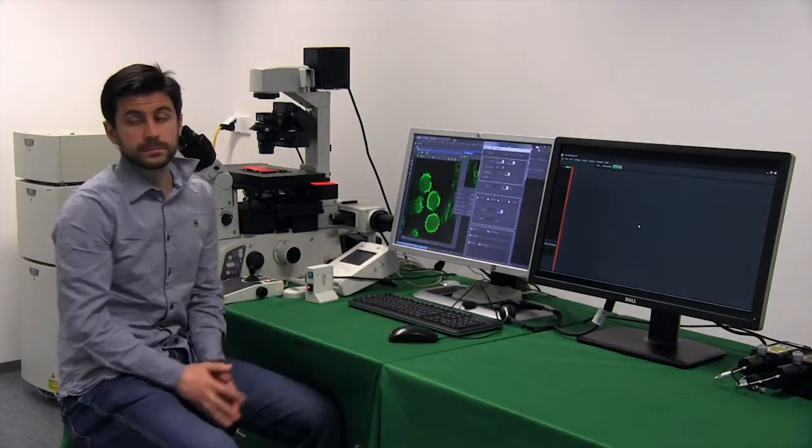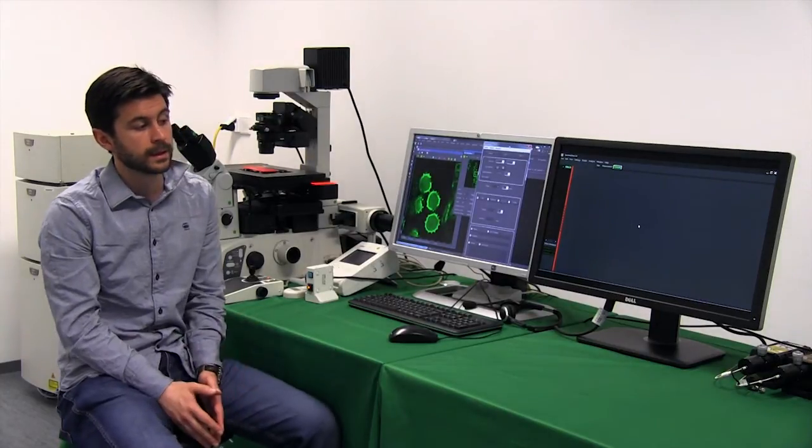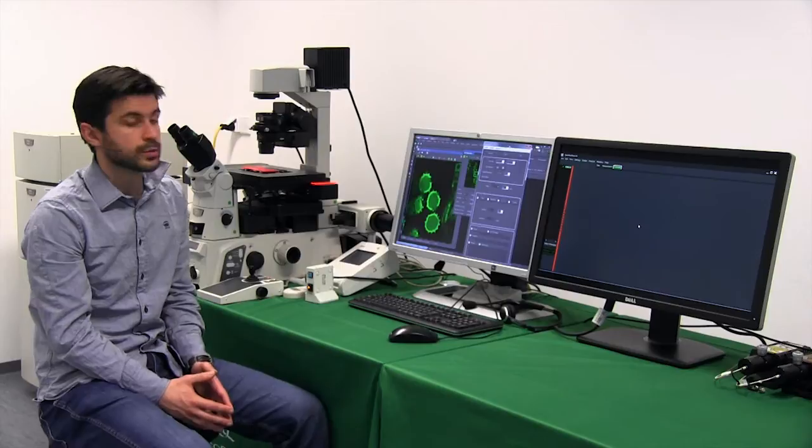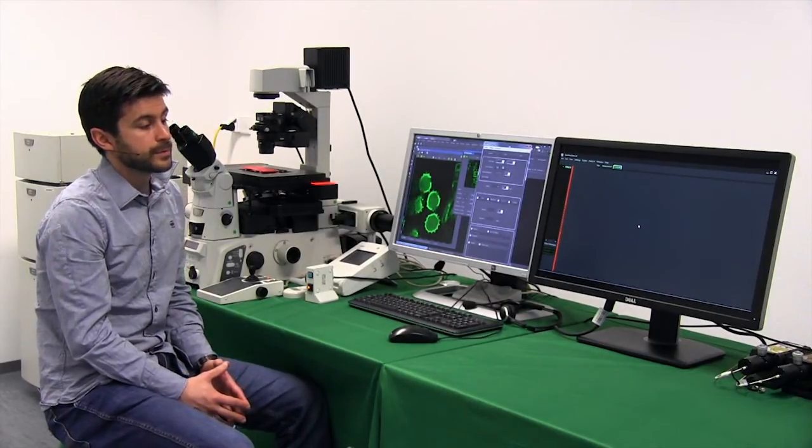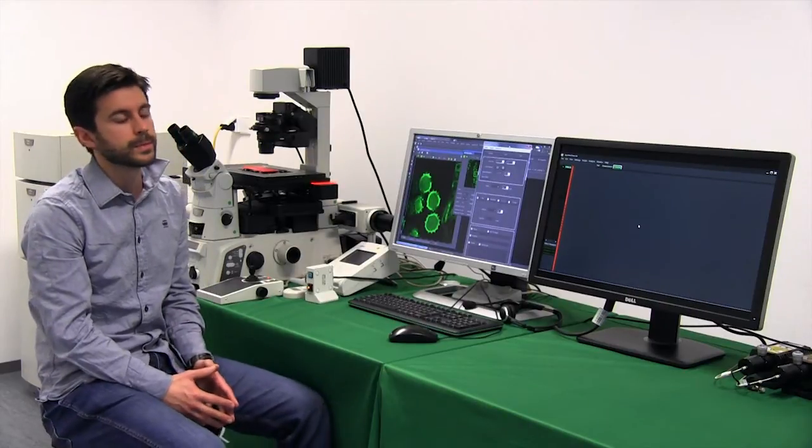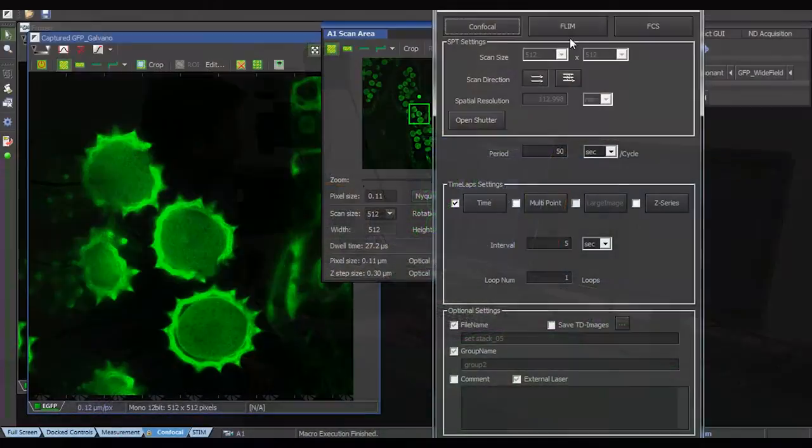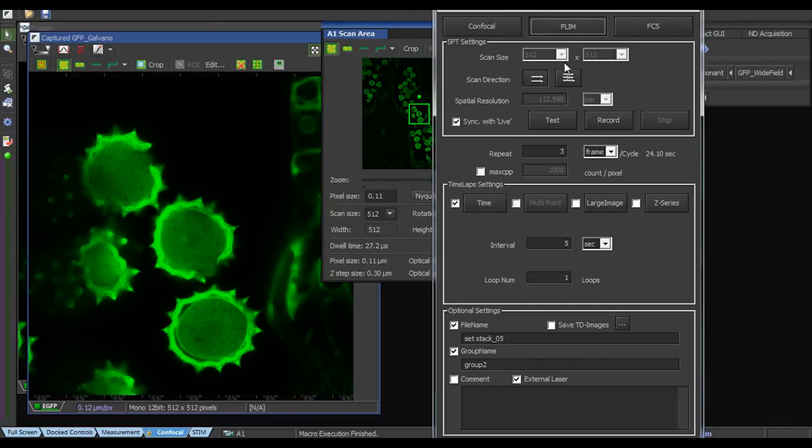In FLIM measurements there are two things we have to control. Most importantly the first one is the repetition rate of the laser we want to pulse with. We have to pick a repetition rate which is low enough to allow the whole population to decay. And the second one is to control the count rate. Due to the dead time of the electronics we have to keep the count rate to 5-10% of the excitation rate depending on how accurate we want to be and depending if we're doing FRET or molecular sensing.